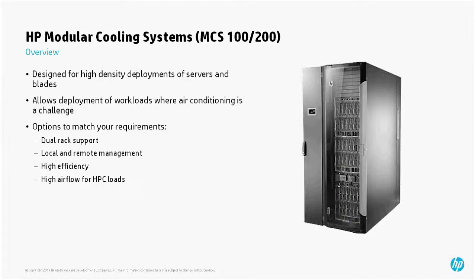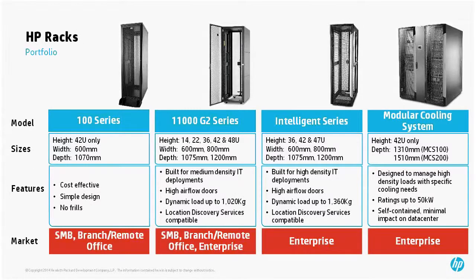All right, so here's the one - you can see on the far right here, there's two racks with that single unit. That's really what we see more often than not, the MCS 200, where you have two racks fully loaded with equipment. It's designed to cool both those racks up to 50 kW of cooling, and that's not split any particular way - you can do 50 kW in one rack and not the two, or if you do the two from one unit, it can be 25 and 25, or 45 and 5. It can do any which way, however you need it to do it.